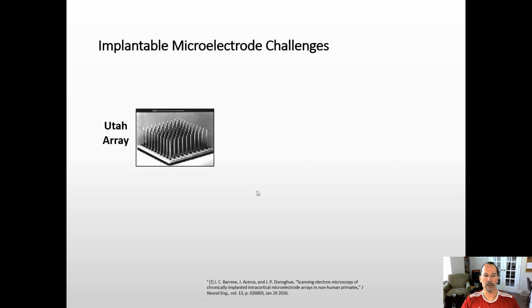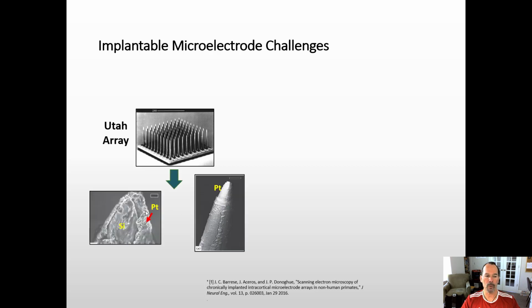So what are some of the challenges? And again, going back to this, this is an old photo of the University of Utah Intracortical Array. Quite important because it's the only device I believe in the US that's been FDA approved for human use for those that are chronically or terminally ill. So what happens over time? Well, we can have these platinum-coated tips, and there are Parylene C-coated shanks. We can have the platinum corrode, exposing cytotoxic or toxic silicon to the brain, which causes failure, or we can have a failure in the coating, which does the same thing.